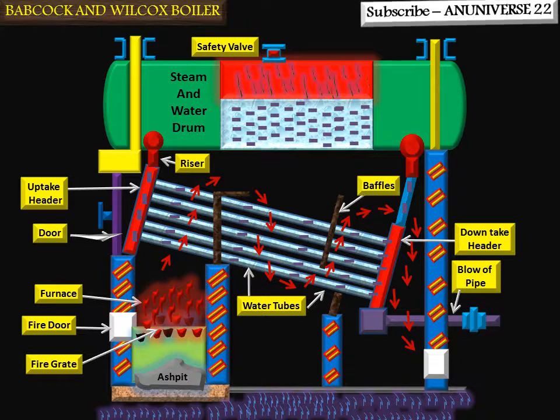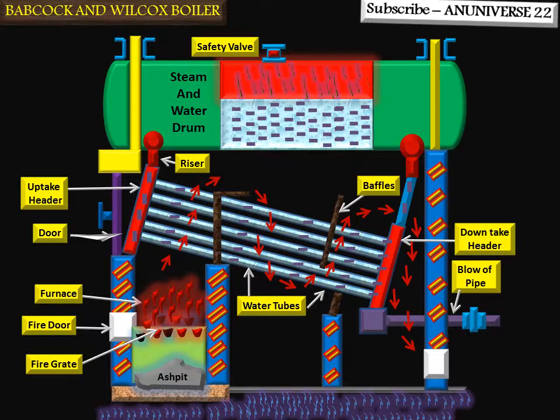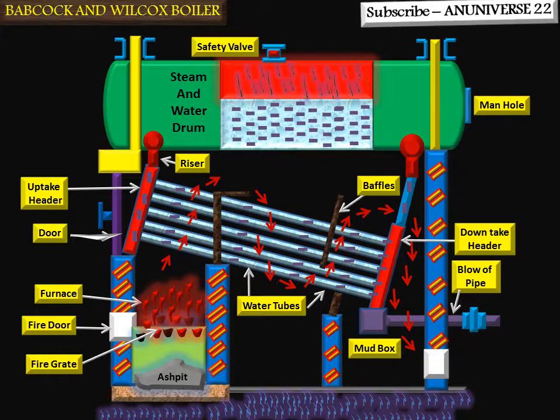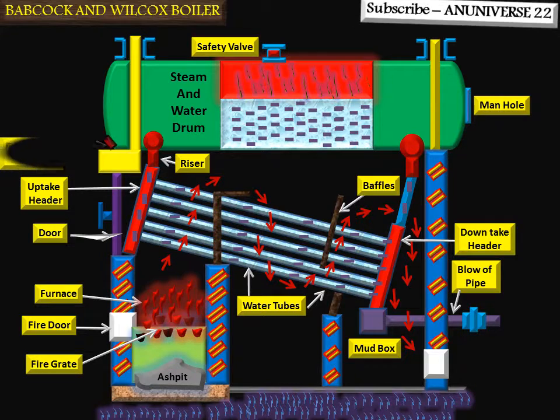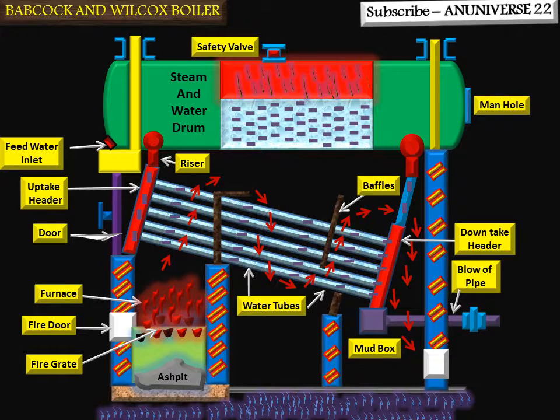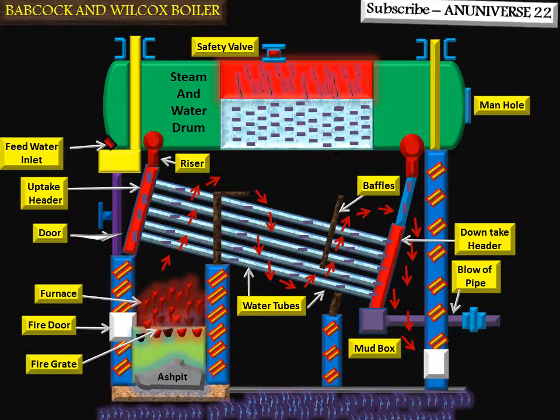This is the blow-off cock. The main function of the blow-off cock is to empty the boiler if required and discharge the mud and scale accumulated at the bottom of the boiler. The manhole provides an opening through which a man can enter the boiler for cleaning and inspection purposes. The feed check valve allows feed water under pressure to pass into the boiler and prevents water from escaping back in the event of failure of the feed pump.